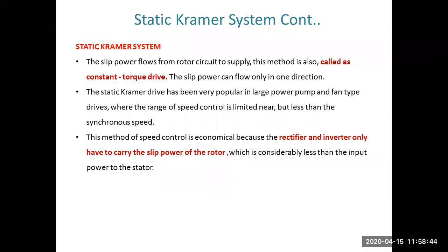The amount which is wasted in the rotor resistance is very small in comparison to the total input supply power. In our case, the rectifier and inverter are connected at the rotor side, so their power rating is decided on the basis of slip power, which is very small in comparison to the input supply power. So the rating of the rectifier and inverter is reduced, hence their cost is also reduced. This is the benefit of the static Kramer system.